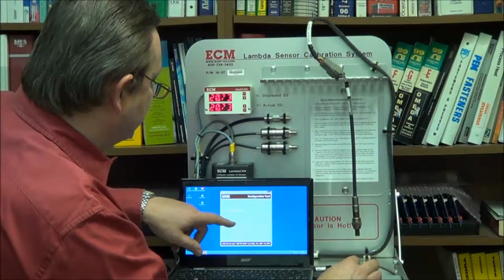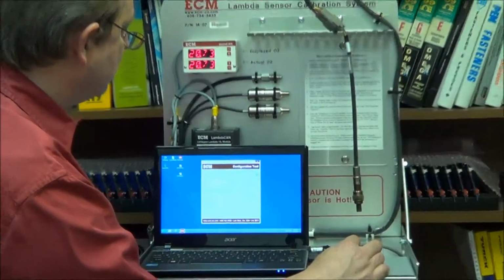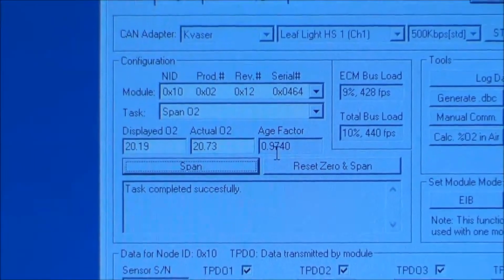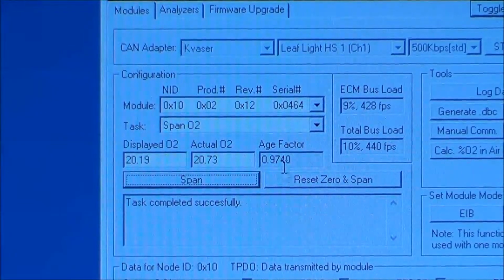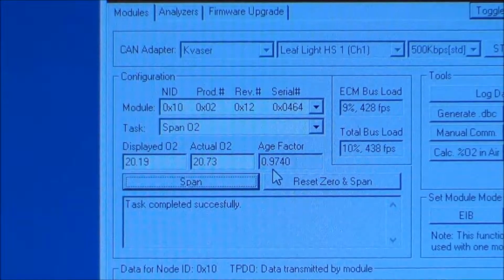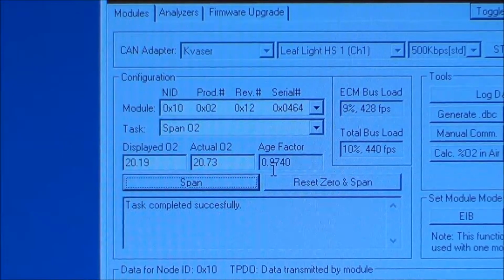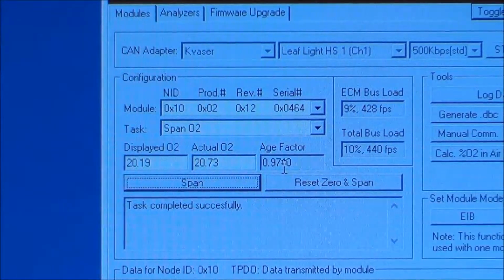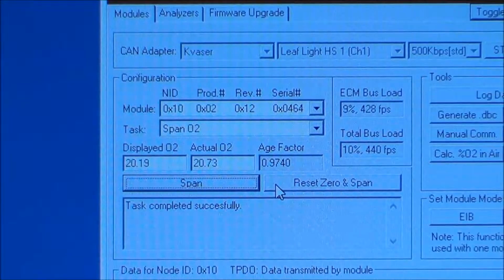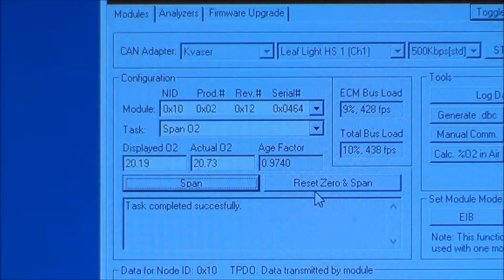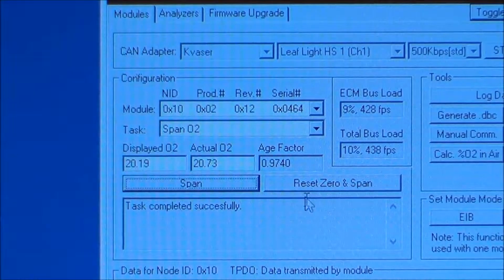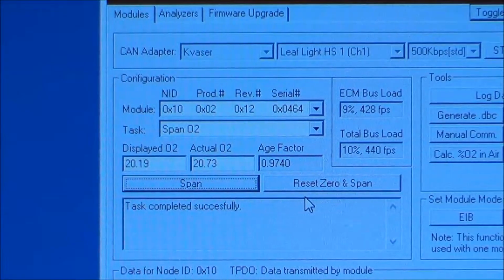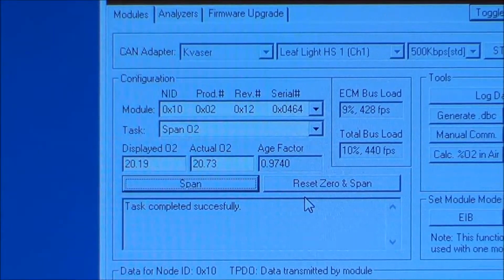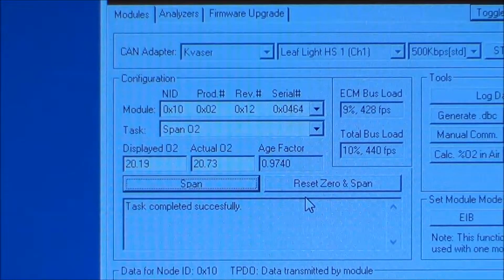After the calibration, you're going to get an age factor. If a sensor is new, the age factor is 1. As the sensor ages, the number will go down. We recommend that when the age factor gets to 0.8, the sensor isn't used any longer. If you mess up the spanning, you can reset the span, and the age factor will pop back to 1, and then you can repeat it again. You can span and reset a sensor as many times as you want.